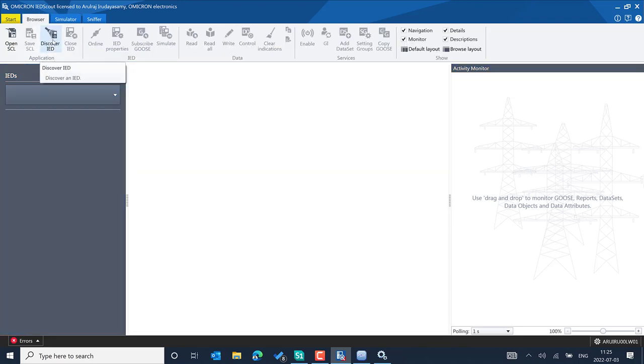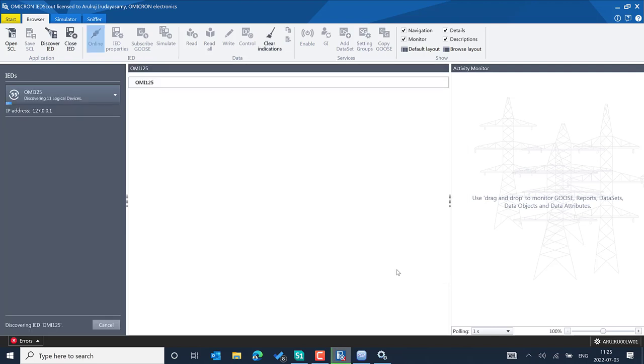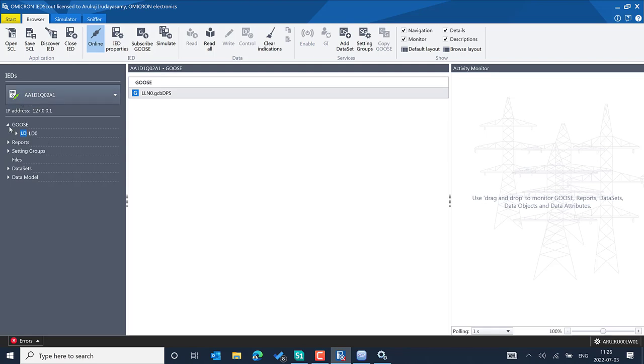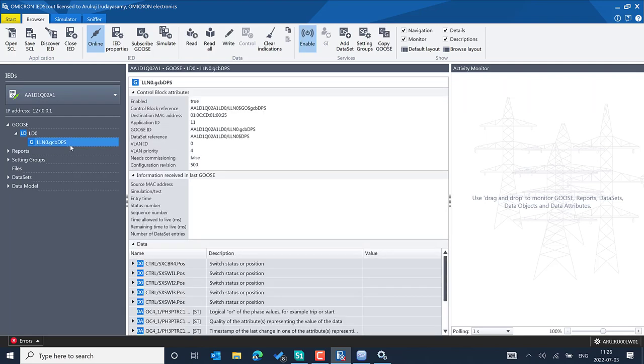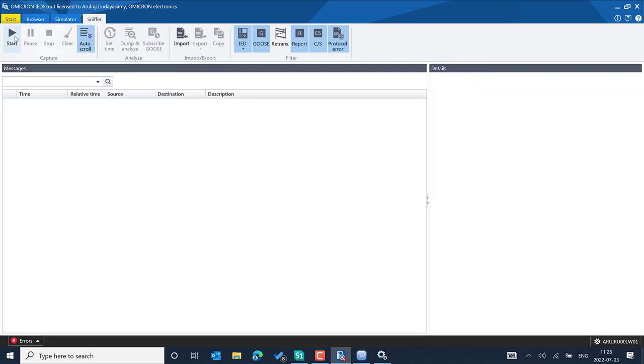You can also go to the Browser section. The simulated IED can be discovered — provide the localhost IP address 127.0.0.1 and the default port parameters, then select Discover. It will discover the simulated IED. This is exactly how the real environment also looks when you provide an IP address and discover an IED. You can see the GOOSE control block, and subscribe to it. GOOSE messages start being received by IED Scout — you can see the simulation flag is enabled.